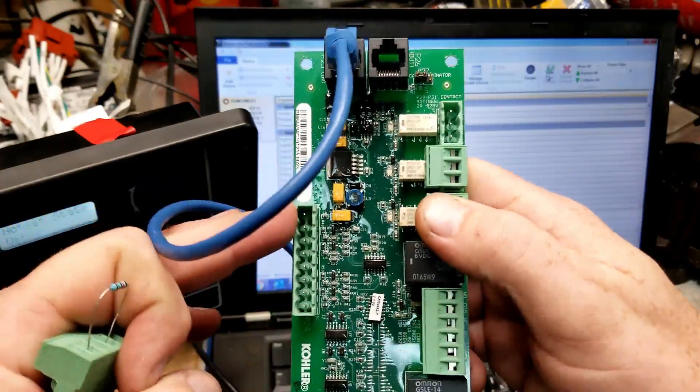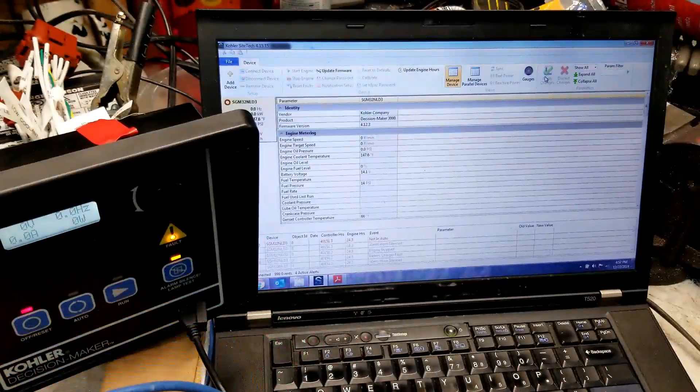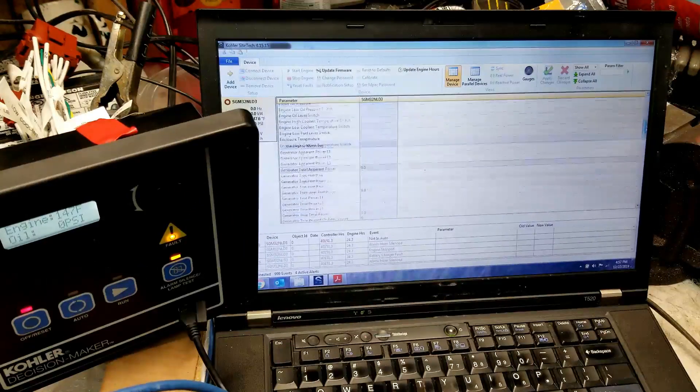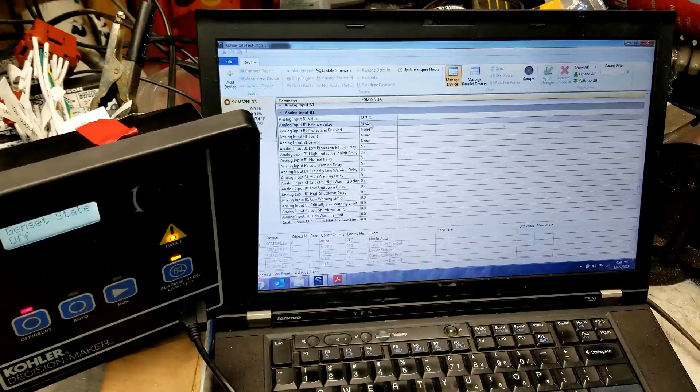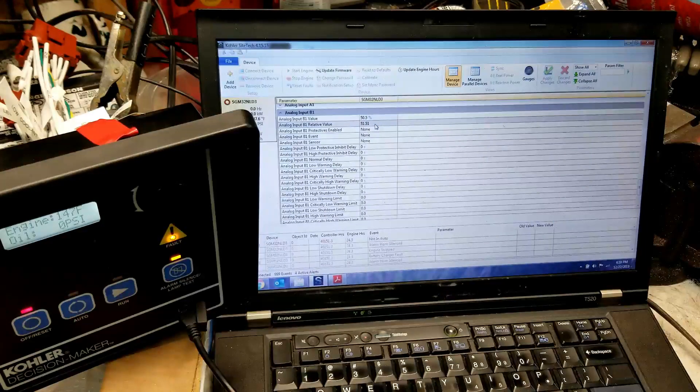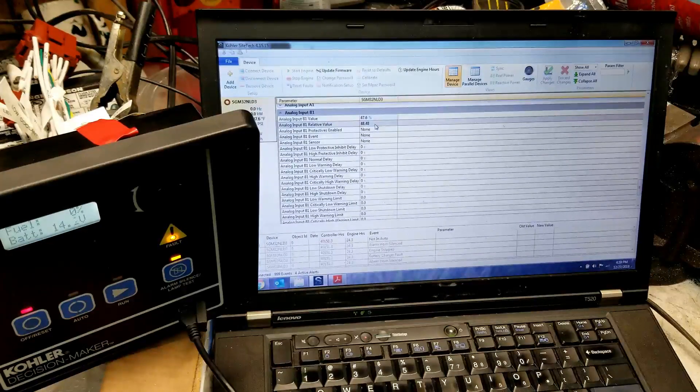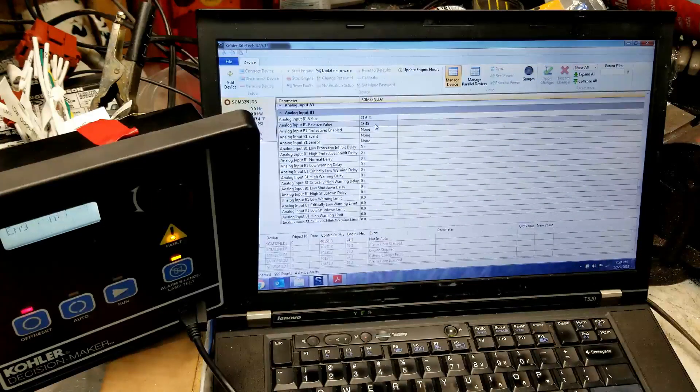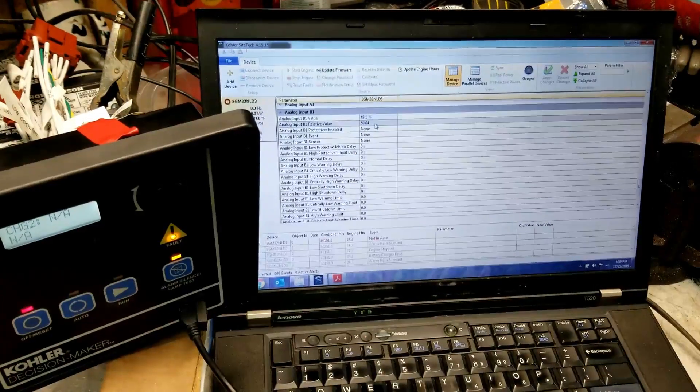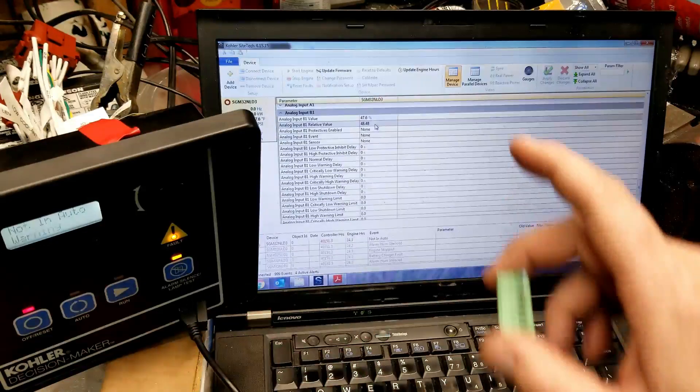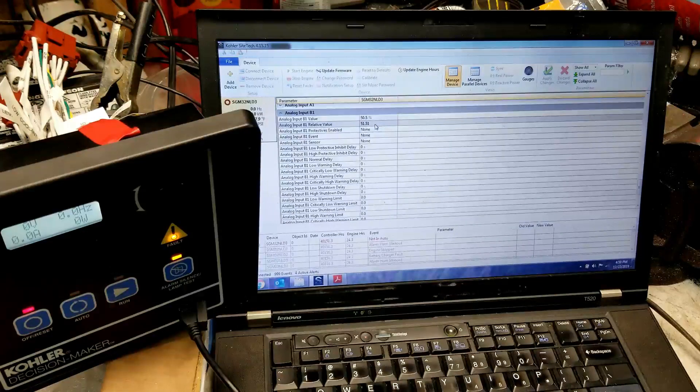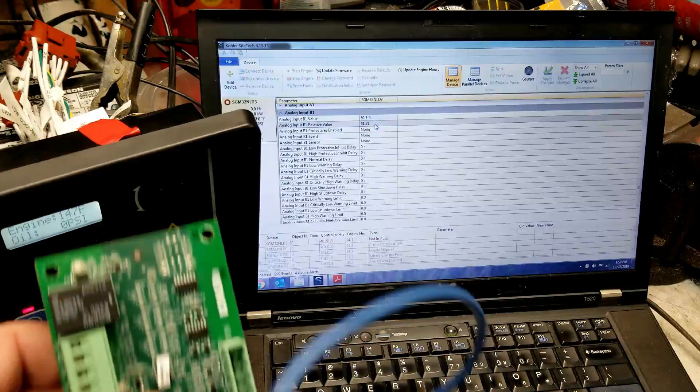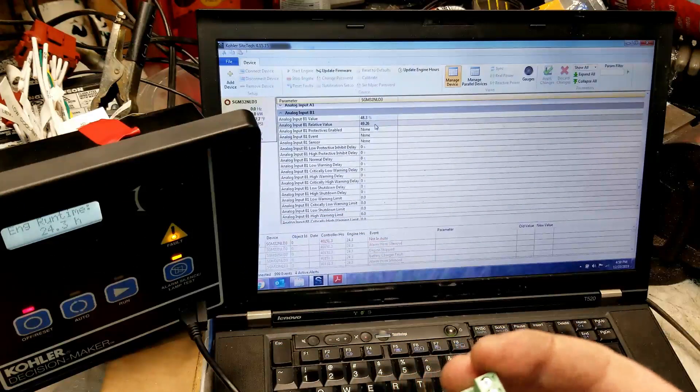So, like I said, this is analog input B1, analog input B2. So since we're all loaded up here, let's scroll down to the bottom. All right, we got down to the bottom. See how it says, right here, says 49.65% and around 51 around there. The reason why it says that is it's kind of floating off in a never-never land with just picking up phantom voltages on the board. All electronics do this. I believe the reason why this floats around 50% is because 50% is a pretty neutral number. And they have internal resistance set that way on this board so that it will float around there.